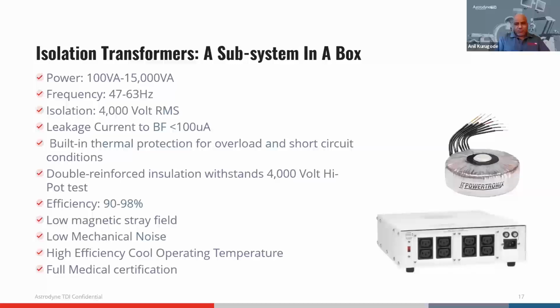The good news is this transformer actually limits the leakage current because it's structurally such that it doesn't have too much capacitance from in to out, and that is all that is needed to control the leakage current. They also put inside what's called a Faraday shield, connected to earth. So whatever leakage currents happen, they happen within the hazardous circuit, but won't go to the patient side, the isolated circuit.